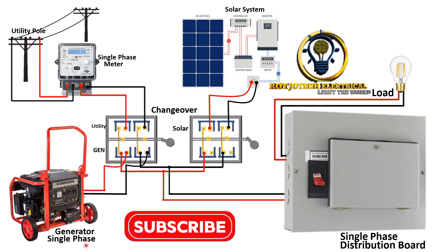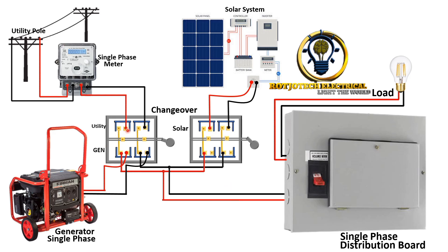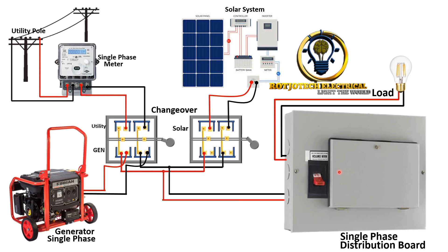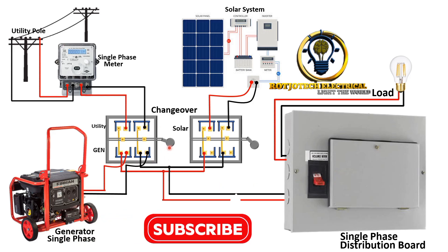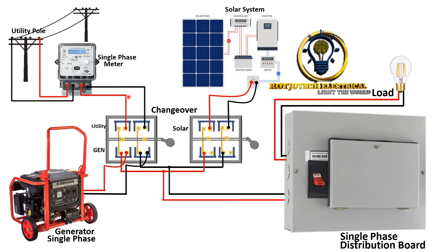The most important thing to be conscious of in this connection is this: when you are using one changeover switch, the other must be on neutral — meaning it is not connected to any side. For example, if you want to use this changeover switch for utility or generator, the other must be in the middle, not connected to solar. Because if the solar changeover is switched on and you also switch this one to utility or generator, you are connecting two power sources together, and it's going to be a disaster.